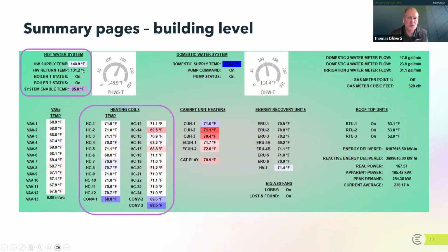And when I say lost, it's being used by the system, hopefully for the right purpose of heating the building. It's a little bit surprising because of the mild temperatures on this particular day, but that's what this is telling you when you look at these particular numbers. I also want to introduce a new idea that I haven't mentioned yet, what's called an enable temperature or an enable set point. Because this is a hot water system, anytime the outside air temperature is less than 85 degrees, this system is going to work. So the heat would be available to run in this particular building. And you'll hear me come back to this in another couple of examples.